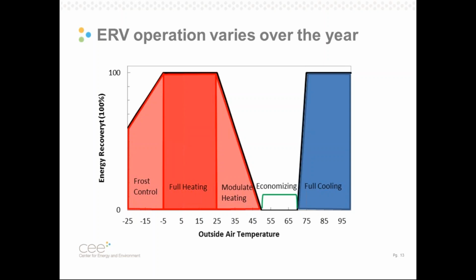This preconditions the outside air and lowers the load on the cooling coils. So our cooling system sees less peak load, and we save energy by running it less. When we're still in cooling mode, but the temperatures are more mild, typically referred to as an economizer period, now our outside air temperatures are actually less than our building temperatures, but we still need cooling.